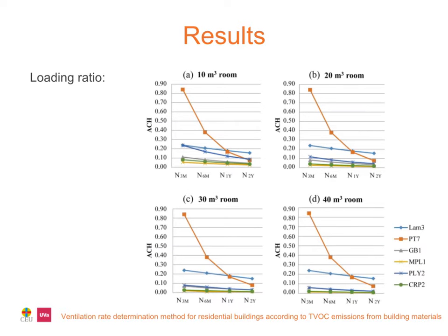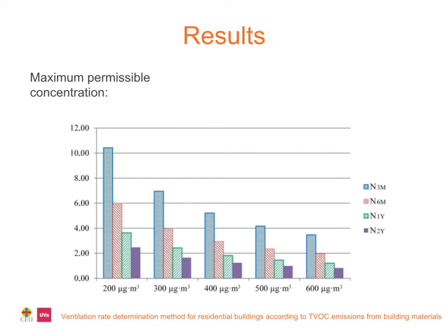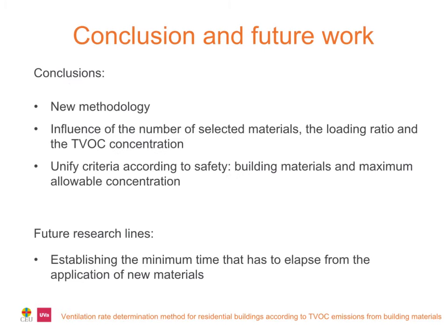When modifying the volume in 10, 20, 30, and 40 cubic meters, the loading ratio varied as well, and also the air exchange rate needed. The figure shows the decrease in the calculated ventilation rate when considering less restrictive requirements, which accept a higher maximum concentration.